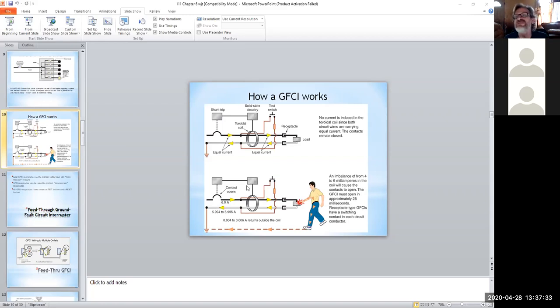It's a fairly easy principle, but yeah, they do have active circuitry to them, and that's why a lot of them these days have a little green LED on them to tell that they're functioning or working, and that's why you're supposed to exercise them regularly. So if you go and press the test button and then hit reset and nothing happens, well, chances are your GFI's life has just ended. It happens, especially because there's actual electronics involved, an actual little circuit board in this guy, so over a given amount of time, I'd expect it to fail.